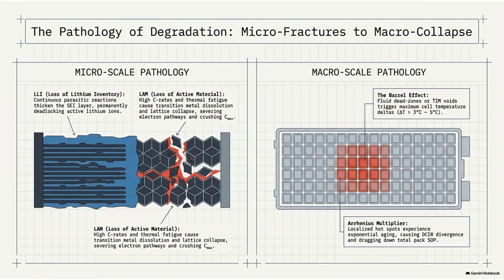Which perfectly applies to a high-voltage architecture. Yeah. Your battery pack is limited by its weakest, most degraded individual cell. Because they're all linked. Right. In an ideal world, all 2,000 cells in a pack would age at the exact same rate. But in reality, manufacturing variances in the cooling architecture create minute thermal gradients. For instance, if the thermal interface material, the thin paste that connected the cell bottom to the liquid cooling plate, has just a millimeter-sized void or an air bubble, the thermal conductivity in that localized spot plummets.